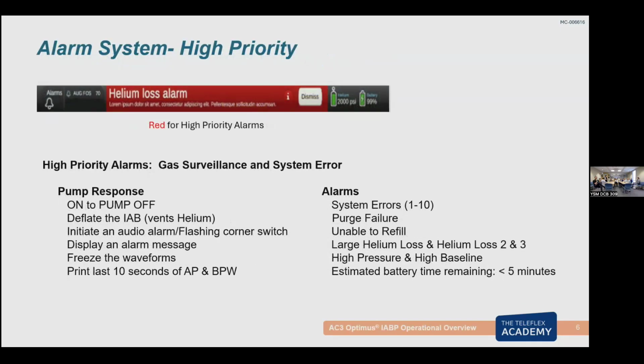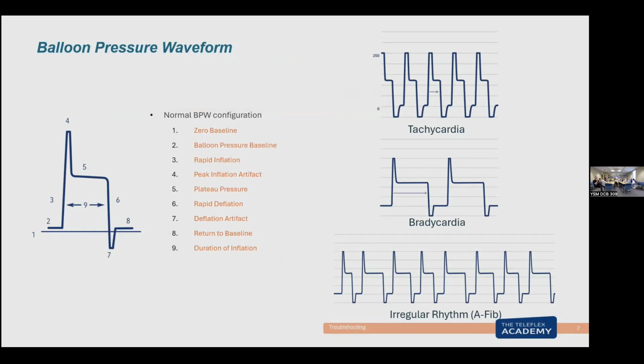The red alarms are the helium alarms, and the pump does stop pumping again. You can also get a red alarm if there's a system error alarm. That's usually a computer issue. If there's something wrong with the computer on the pump, you might get a system error alarm, and the pump does stop pumping for that. There will be a message on the screen, also in a text box, that tells you the troubleshooting for those alarms. So those are the different levels. The helium alarms are based off what's happening to the balloon pressure waveform. You had this on your other pump. However, it was non-calibrated, it was just a picture, so they could not use it to troubleshoot or quantify anything that's going on with the balloon.